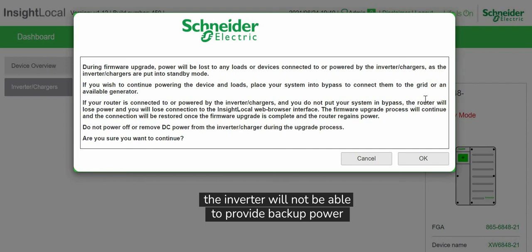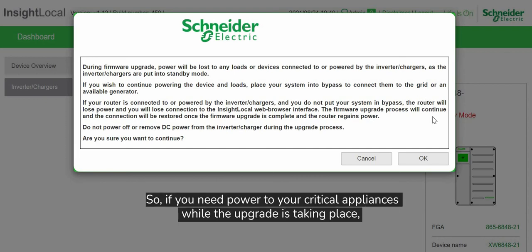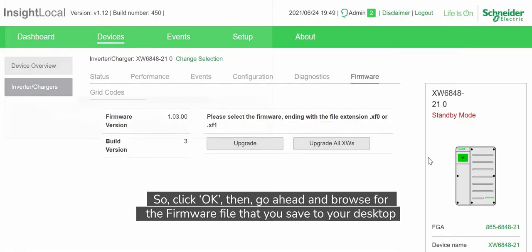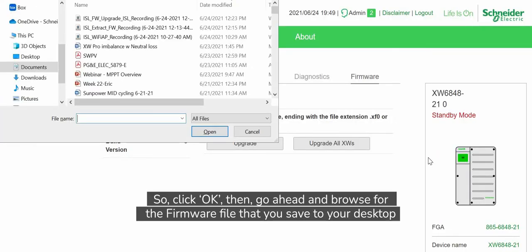So if you need power to your critical appliances while the upgrade is taking place, you'll need to bypass your XW system with either grid or generator power. Click OK and then browse for the firmware file.